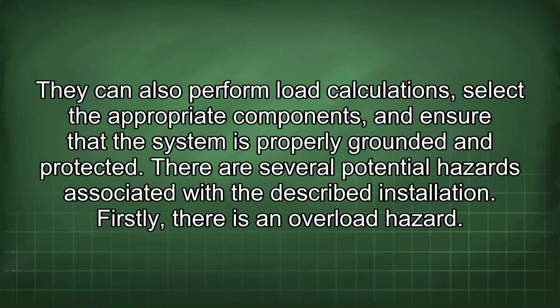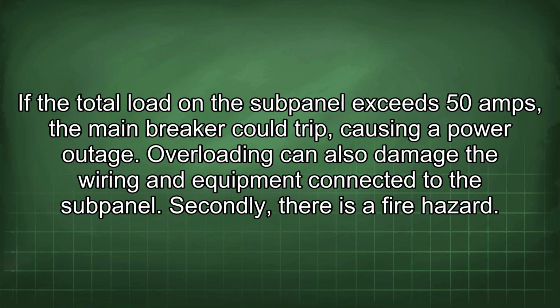Firstly, there is an overload hazard. If the total load in the subpanel exceeds 50 amps, the main breaker could trip, causing a power outage. Overloading can also damage the wiring and equipment connected to the subpanel.